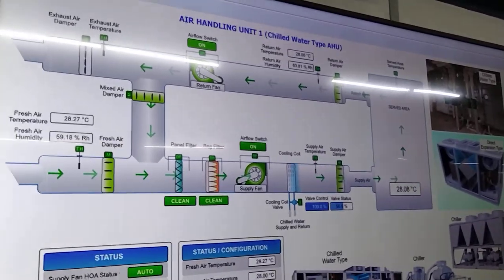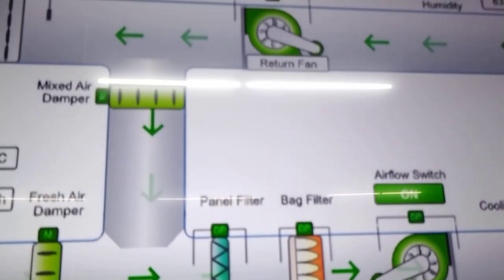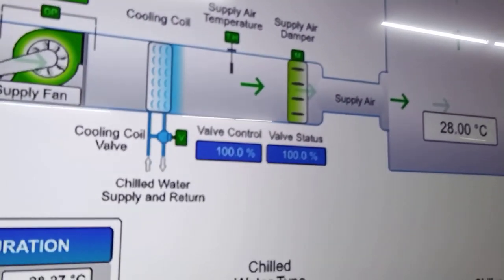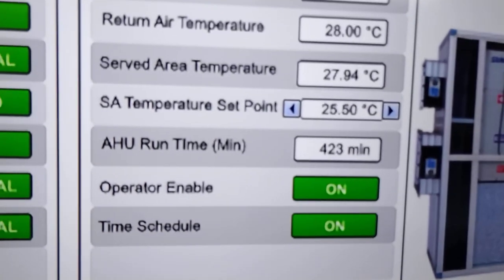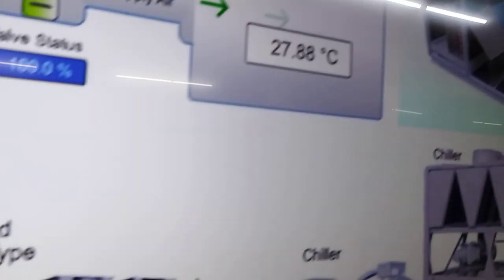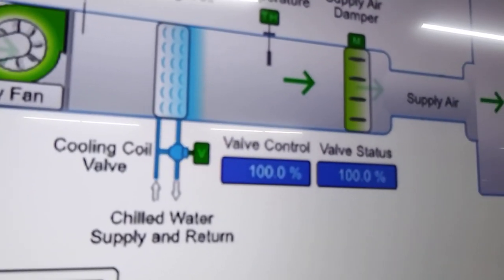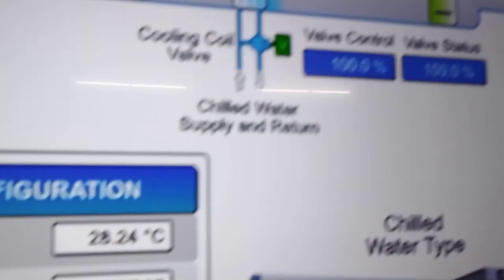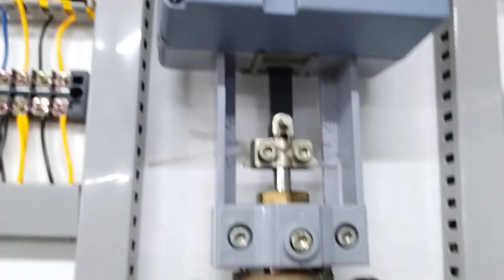Our controls have now turned on our fans. Based on our control logic program, the controllers turned on the fans and we are showing real-time values from the field. The supply fan is already running, then our return fan. We are showing some animation. Our valve is trying to maintain the set point. Our set point is 25.5°C and our actual air temperature is 27°C. The tendency of the valve is to open to allow more chilled water to bring this temperature down to our desired 25.5°C. The valve is already fully open as dictated by our control.